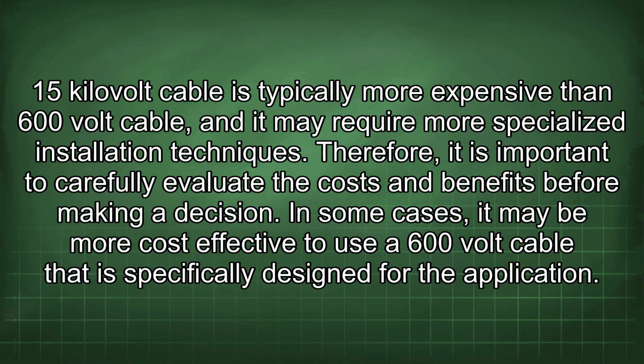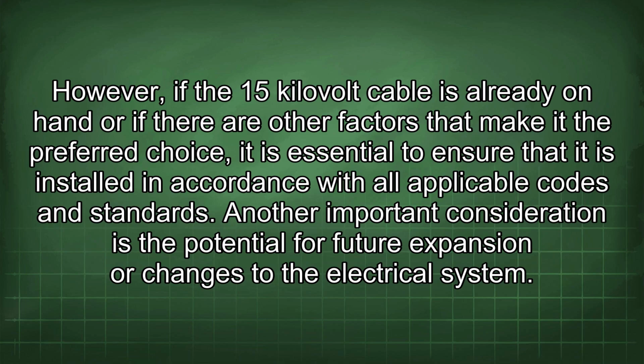In some cases, it may be more cost-effective to use a 600 volt cable that is specifically designed for the application. However, if the 15 kV cable is already on hand, or if there are other factors that make it the preferred choice, it is essential to ensure that it is installed in accordance with all applicable codes and standards.